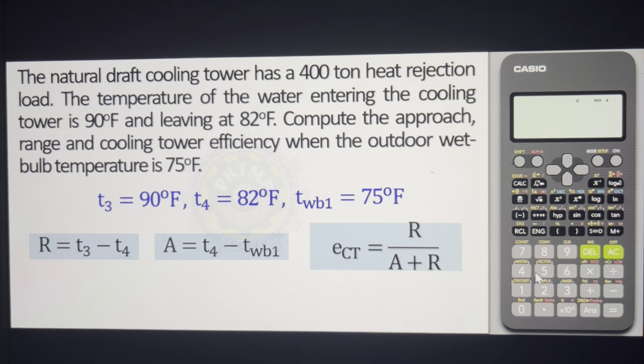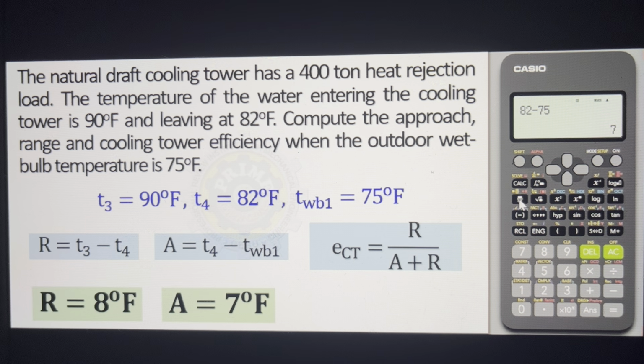Napakabilis po niyan. Para sa range, that is T3, 90 minus T4, 82 — kinalkula pa talaga natin yan — that is 8. Then para sa approach, that is T4, 82 minus wet bulb number 1, 75, which is 7. And finally, para sa cooling tower efficiency, that is the range 8 over approach plus range.